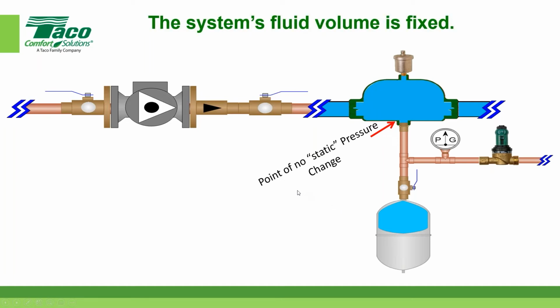Now, here's something that a lot of people can't get their head around. Okay. And I'm going to show you what I mean by that. Let's say I had that big pump, the big one-size-fits-all circulator like our 0013 or 2699 or something to that effect. And I'm looking at this, it's not running, and I'm about to switch it on. You would bet that I could take this needle and move it way to the right by putting that big pump on there and pumping into this point. And most people would agree. I can't see you, but you're probably nodding your head that, yeah, I'm going to move that needle. Now I'm going to say, no, you're not. And I've proven it with a demonstration, and I'm going to prove it now just by an explanation.